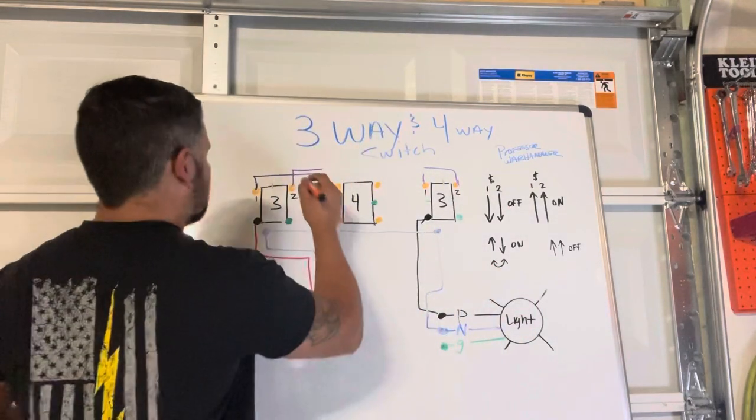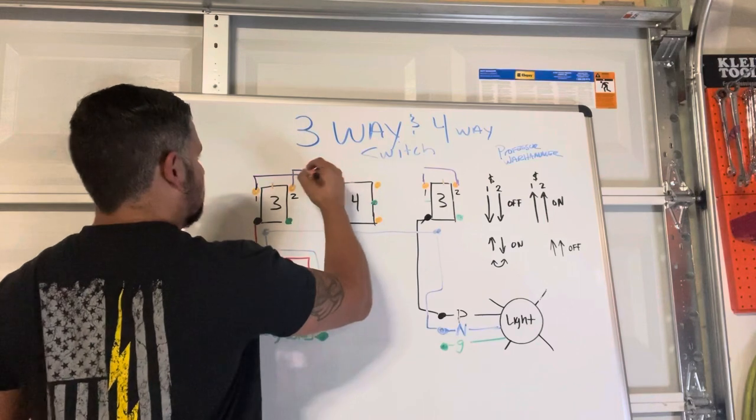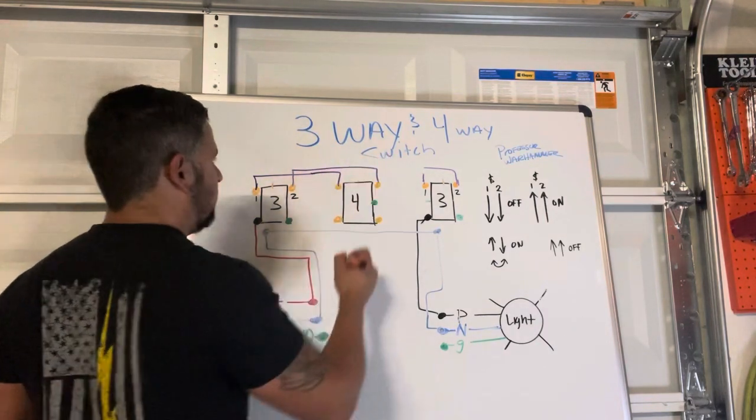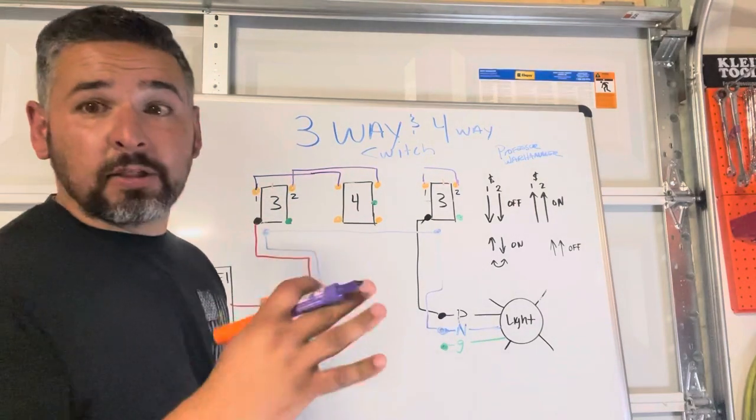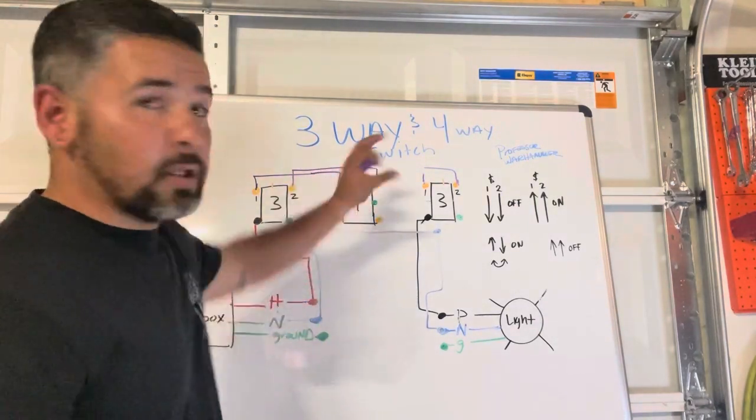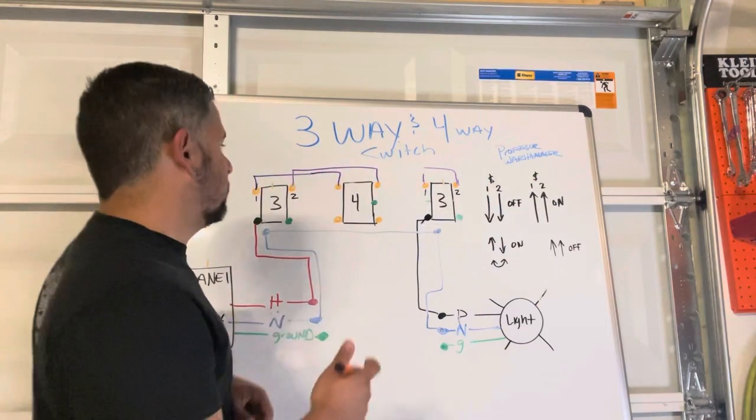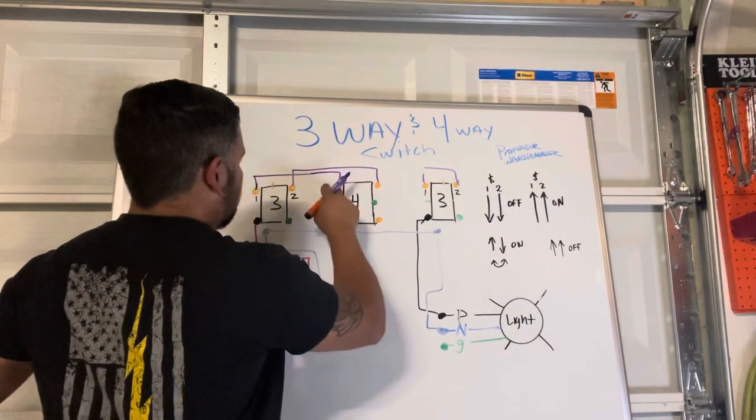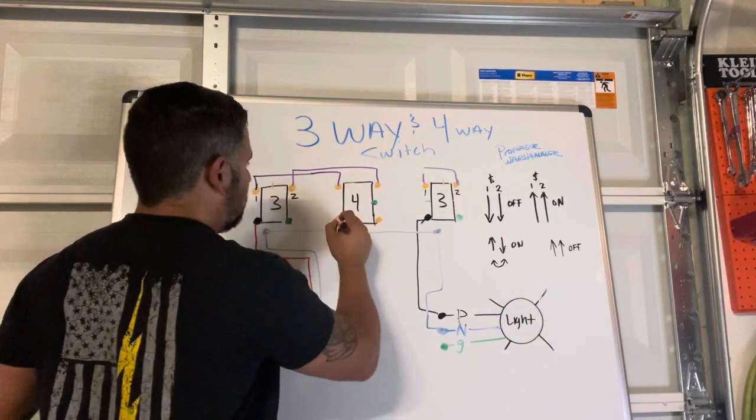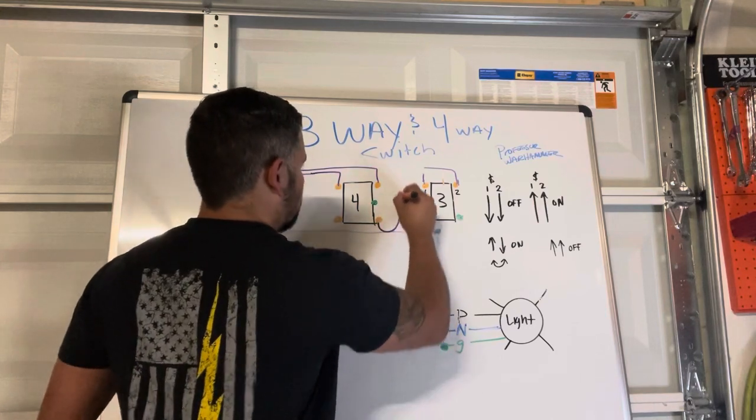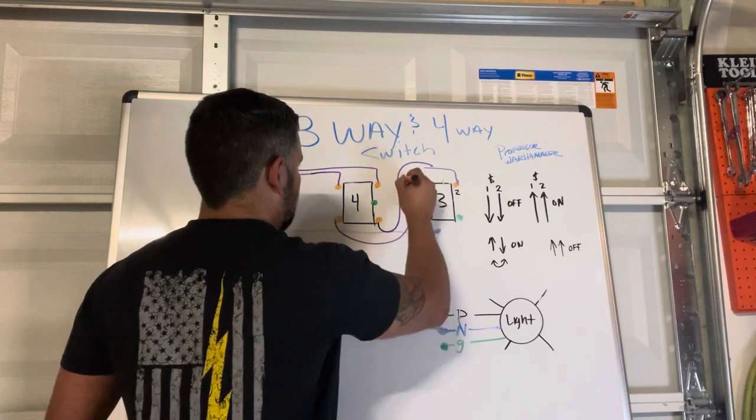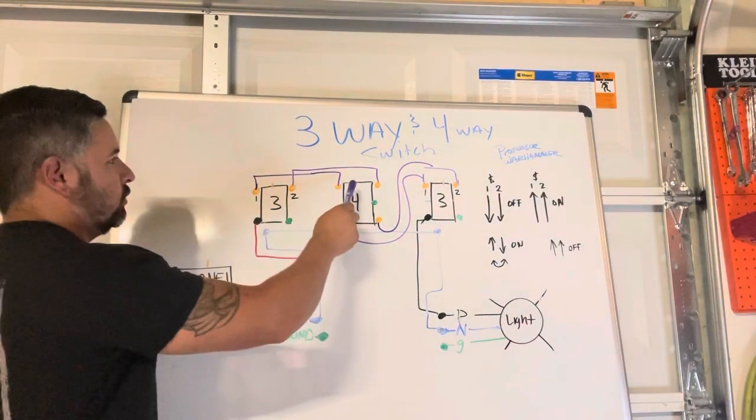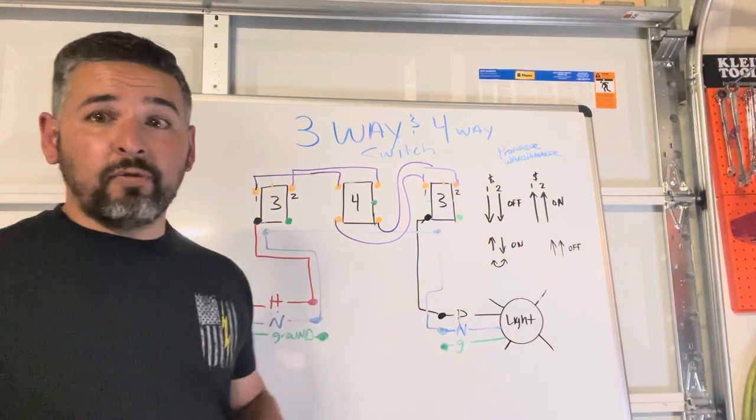Alright, so out of this little deal we're going to have the travelers come to the top set from the first switch. And once again this doesn't matter which way this goes, it can be top or bottom, I'm just doing this for whatever purposes. So we have one and one, two and two, and then right there and right here. So that is how you're going to do a four-way.